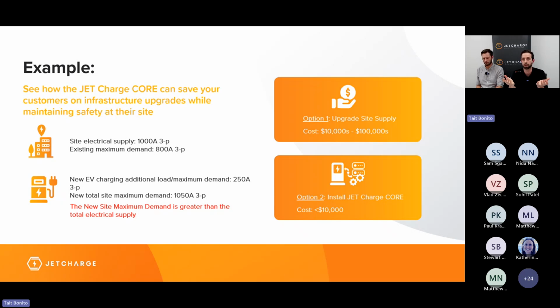And so you can look at the existing supply of 1000 amps and the current maximum demand of 800 amps. You can add the new EV charging maximum demand of 250 amps, and you'll see that that would take the new building maximum demand, once the EV chargers are installed, to 1050 amps, which is greater than the 1000 amp electrical supply. And so that's where, as an electrical contractor, you can work with the customer to discuss two options with them. The first one being upgrading that site supply. So you could upgrade that site supply to 1050 amps or above to make sure you've got additional headroom in the future. But as you all will likely be aware, this is just a really expensive exercise.